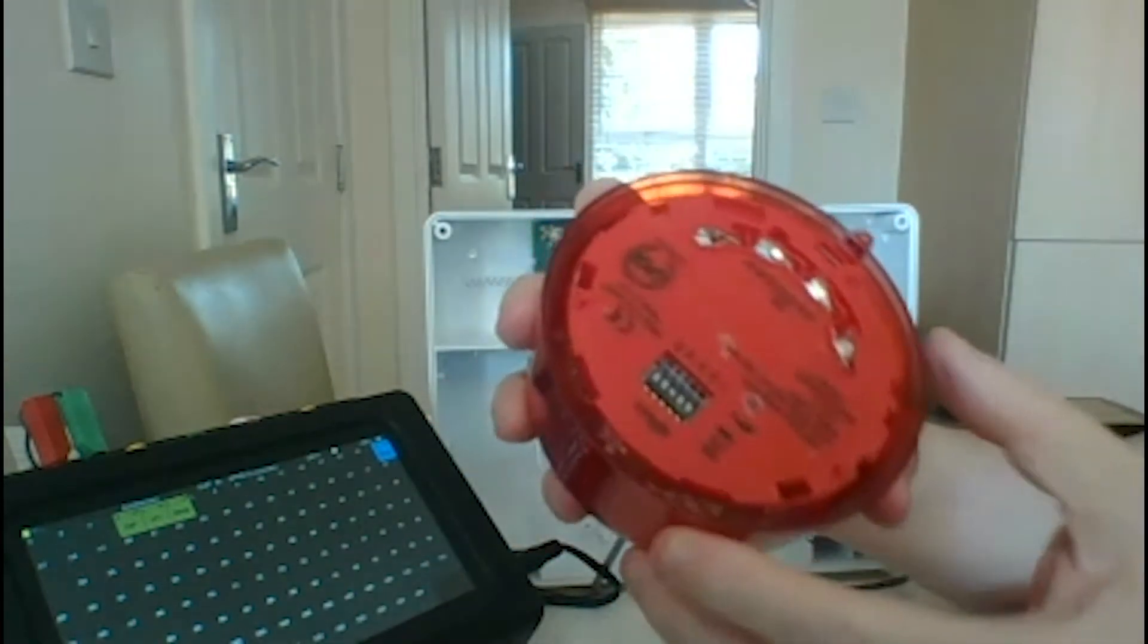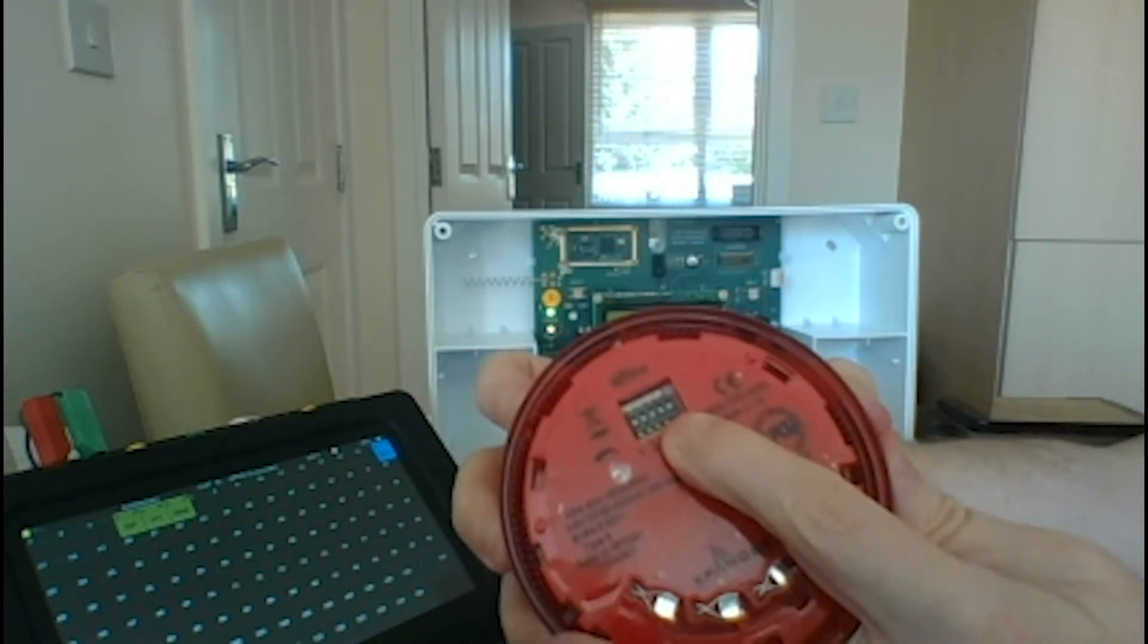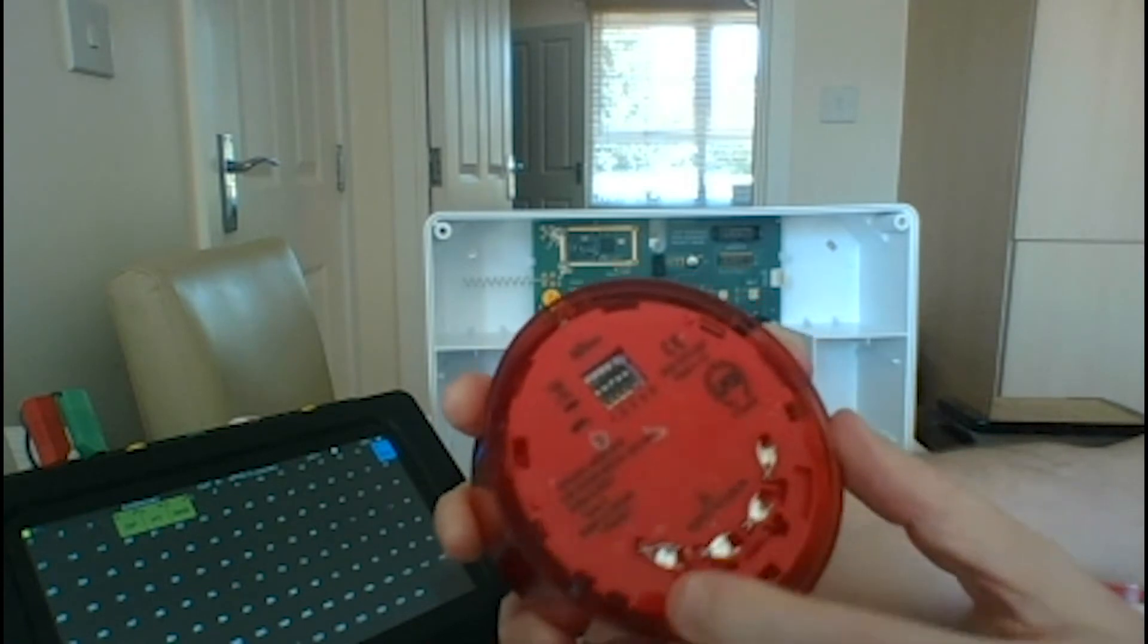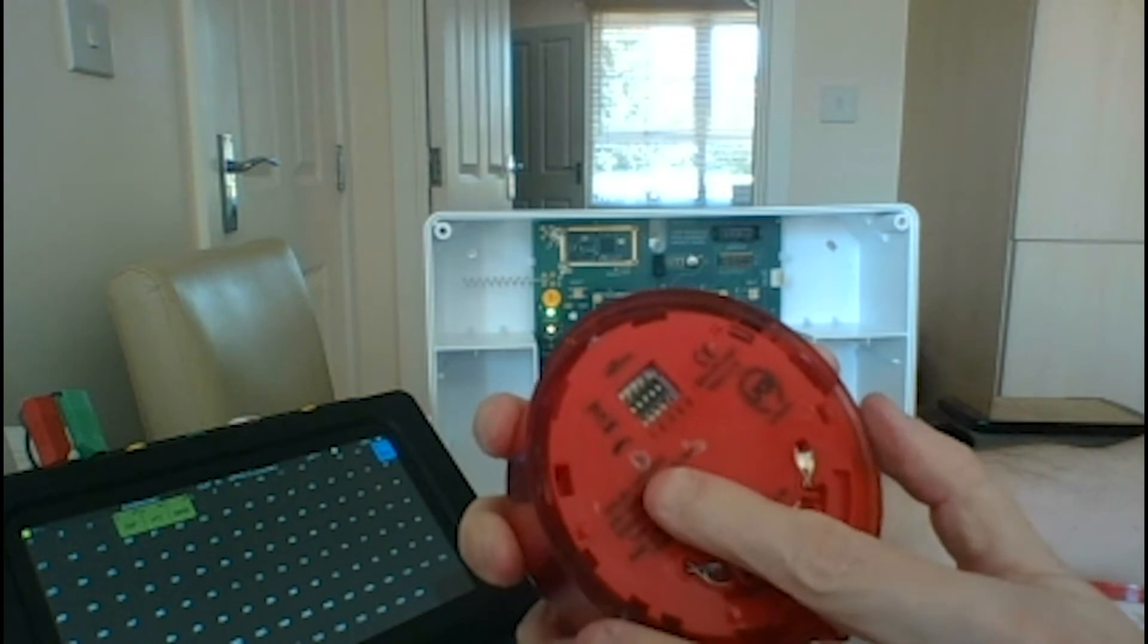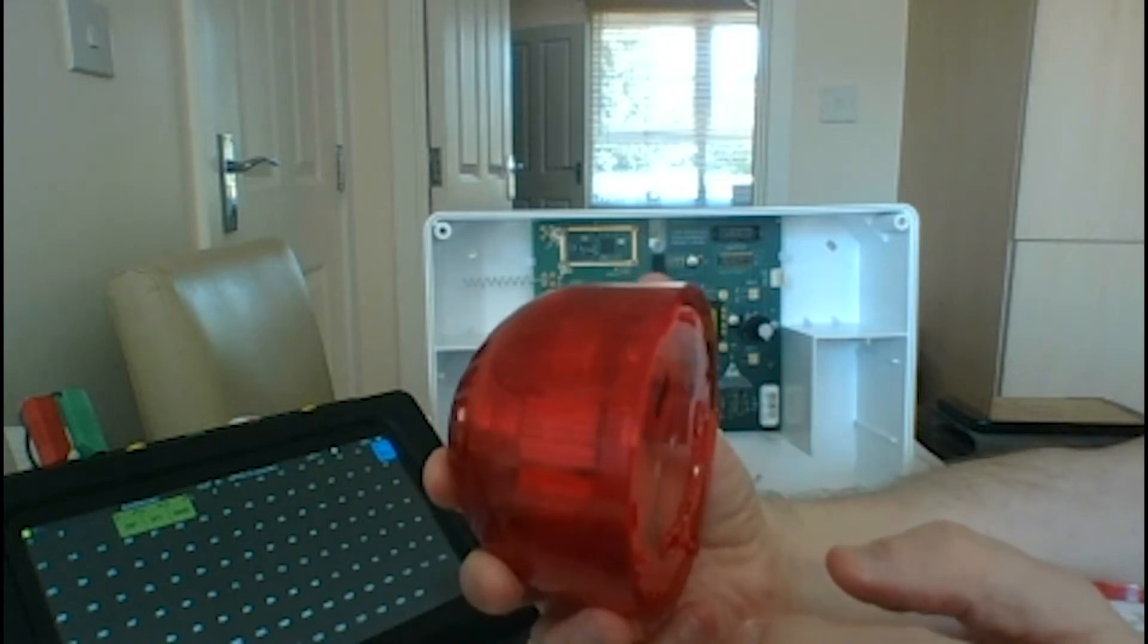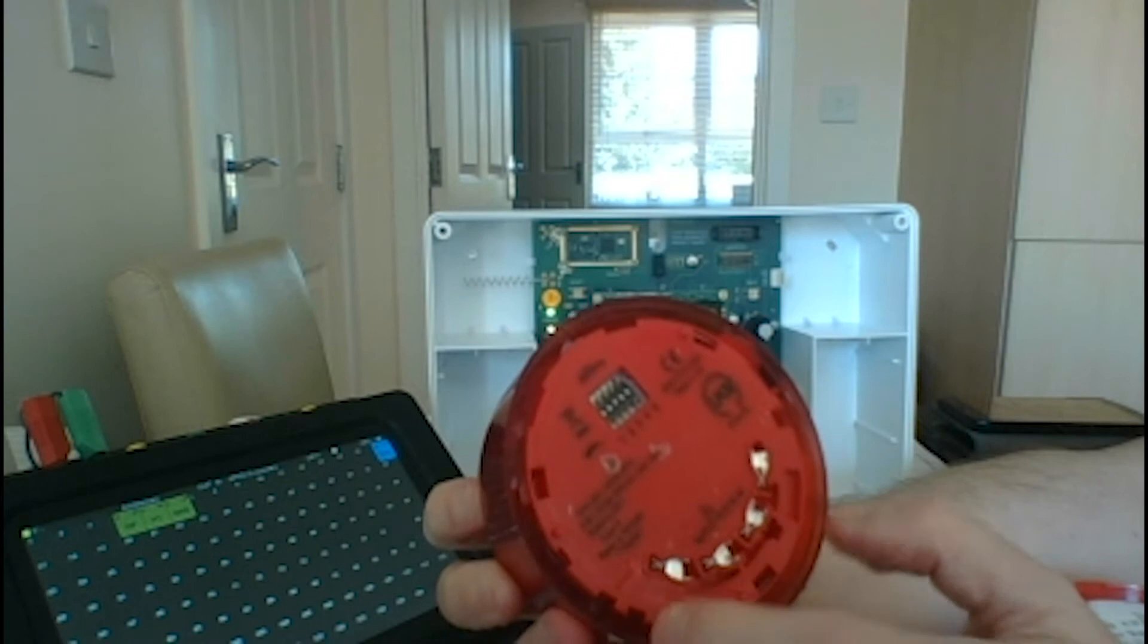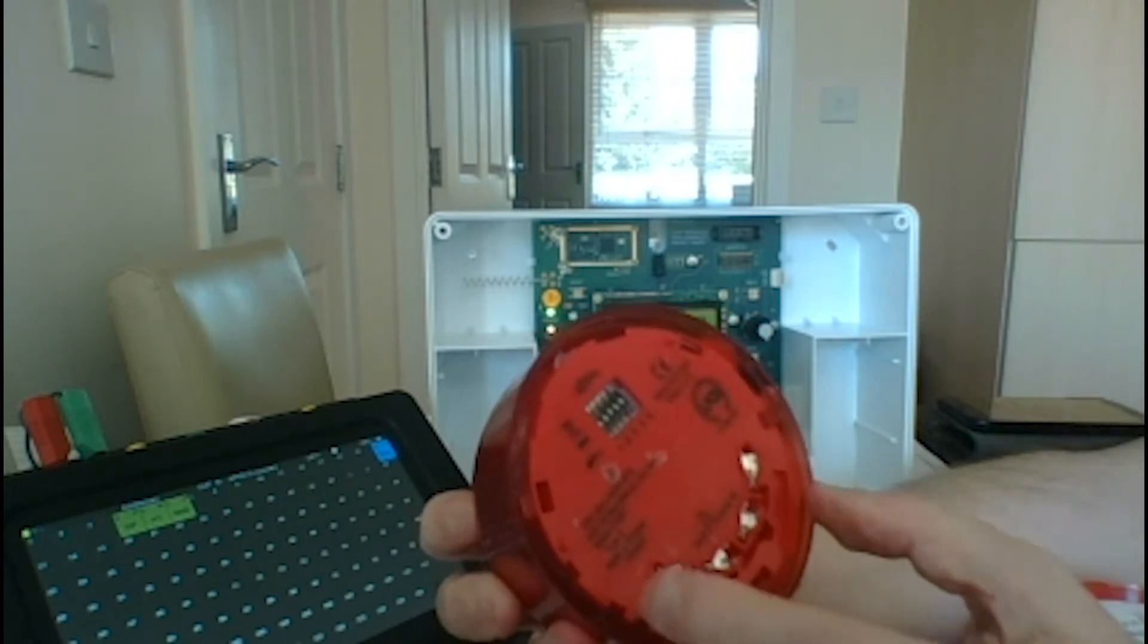You've got the sounder beacon, and inside there's a DIL switch which is used for changing the tone of the sounder. It's set to the Apollo tone as it stands. You've also got a pot on there that you can use to turn the sounder down. The sounder at the moment is set to 100 decibels, but we can turn it down a bit if needed, if it's nearer where somebody's working.